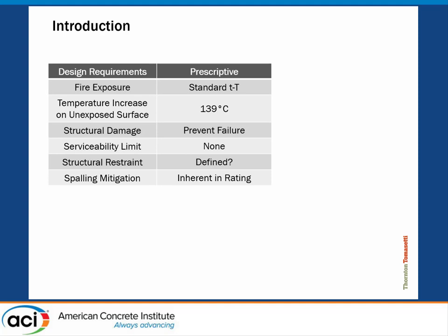We've already talked on performance and fire ratings — your one-hour, two-hour fire ratings that are very typical in design. Embedded in that one- or two-hour fire rating are the following things: for fire exposure, it's the standard time-temperature curve, ASTM E119 that you've already seen. The performance limit is simply that the temperature increase on the unexposed surface can't exceed 139 degrees Celsius from ambient. Structural damage-wise, you just can't have failure — as long as it doesn't fail, you're fine.